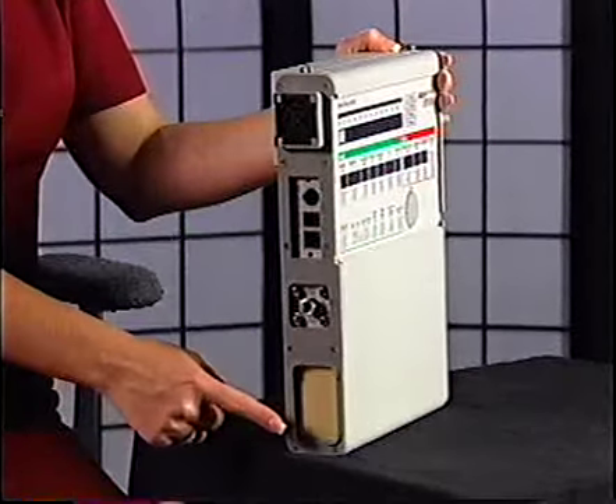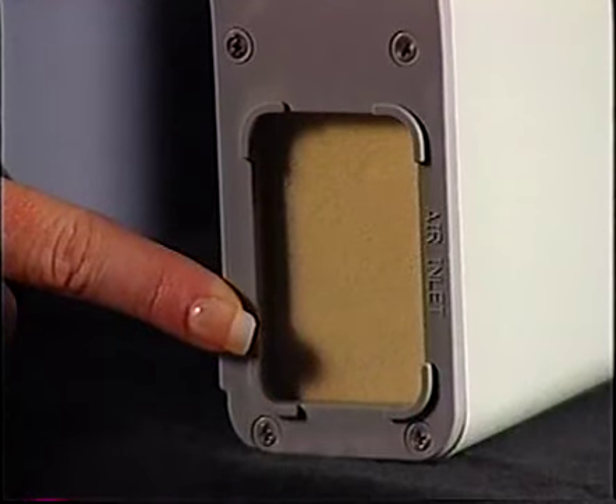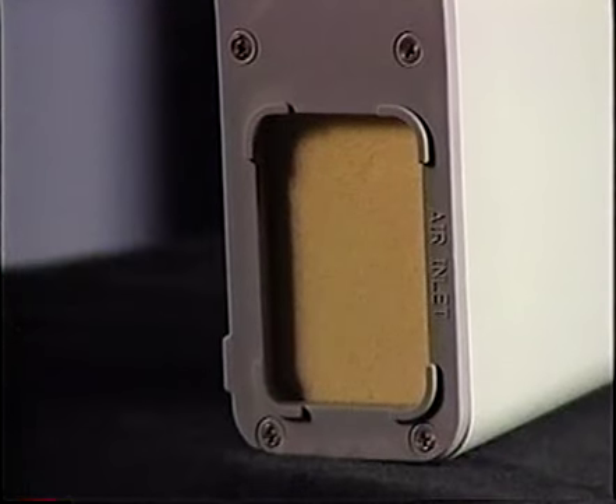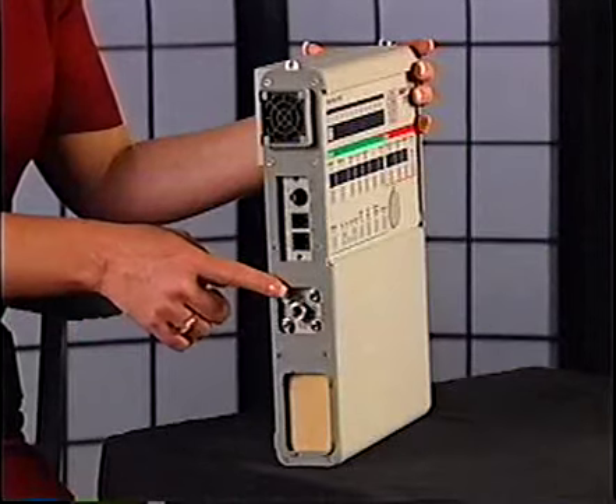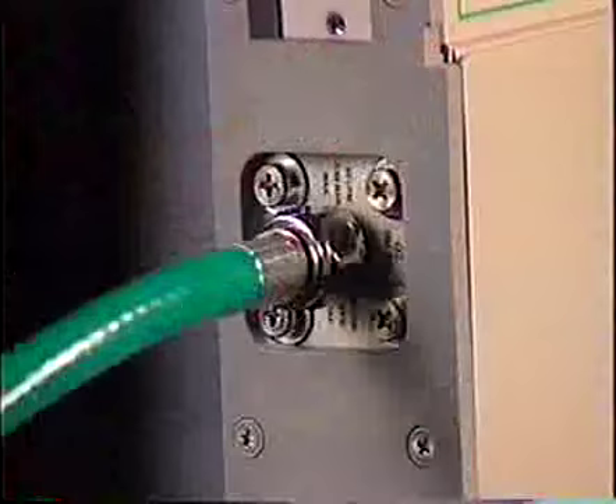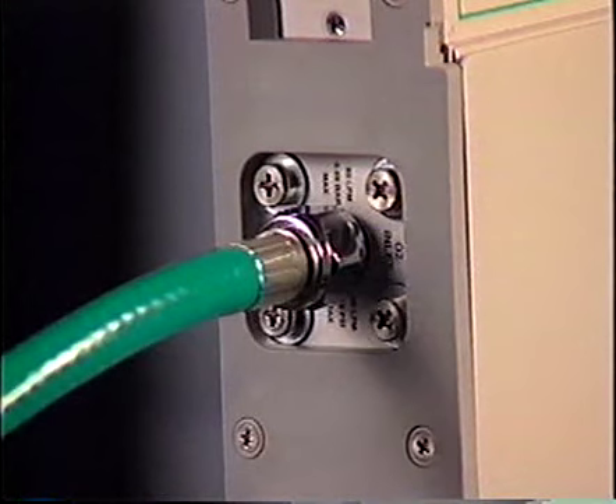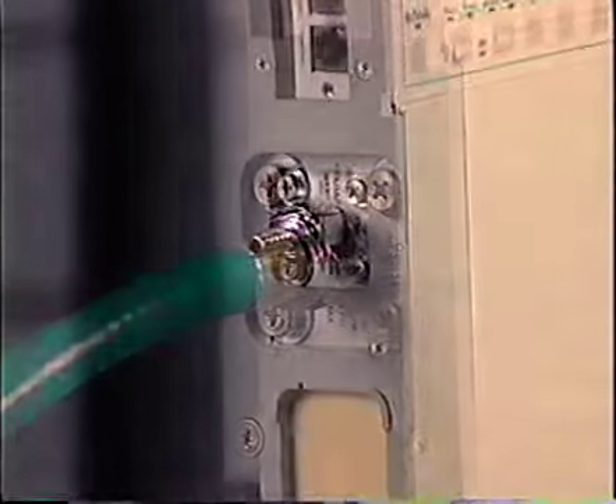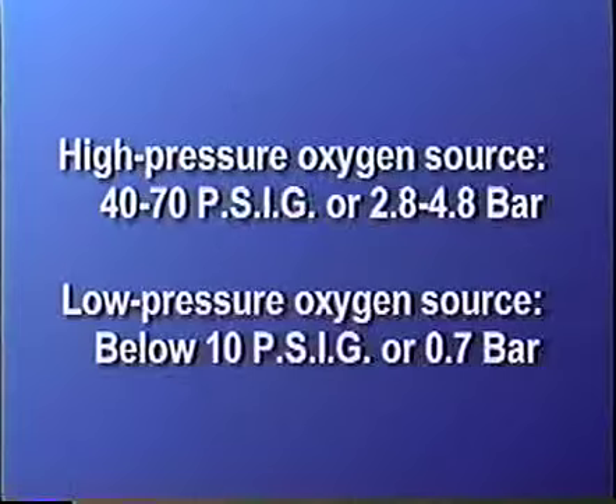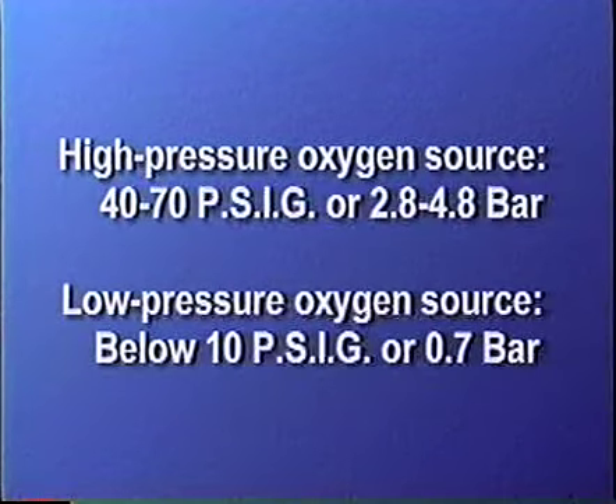On the left side of the ventilator is the inlet filter. It is important not to block this filter because this is where the ventilator draws in room air. Above the inlet filter is the oxygen port. The oxygen port accommodates an oxygen hose or a Christmas tree adapter. If you are using high pressure oxygen, the pressure should be between 40 and 70 psig or 2.8 and 4.8 bar. If you are using a low pressure oxygen source, the pressure should be below 10 psig or 0.7 bar.